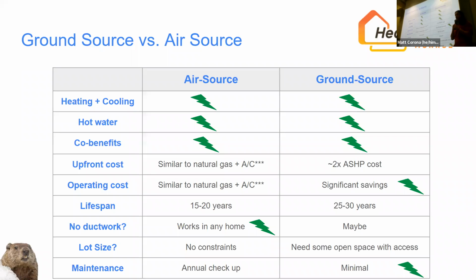Part of the reason for that is because they don't have an outdoor unit exposed to the elements all year round. It doesn't have to work as hard because it's using the stable temperature of the earth to heat your water or air, as opposed to the very cold temperatures outside in winter. So they're more efficient and they last longer. When you replace a ground source system, you don't have to dig the loop field again or drill the wells, so the replacement cost is much cheaper than the initial investment.